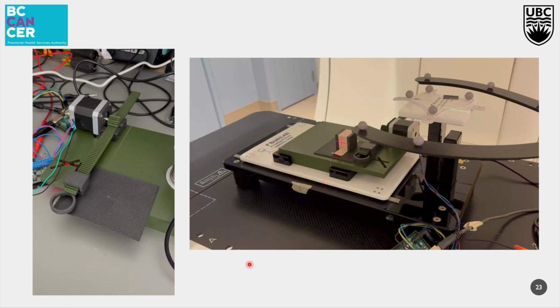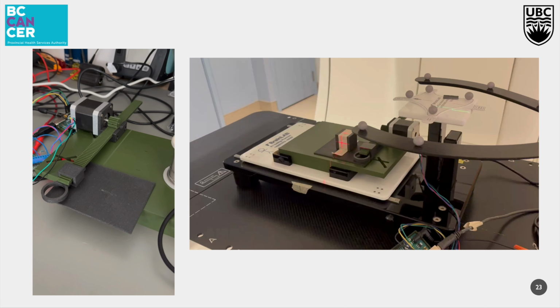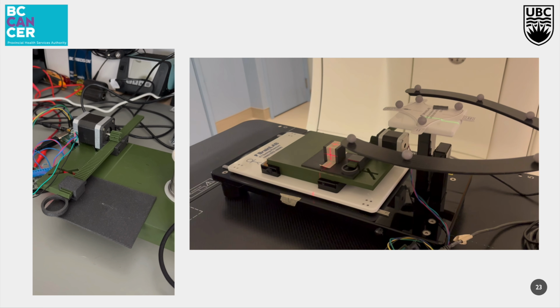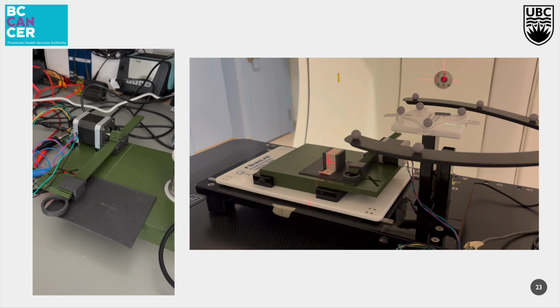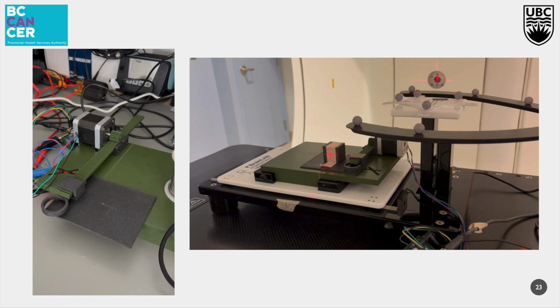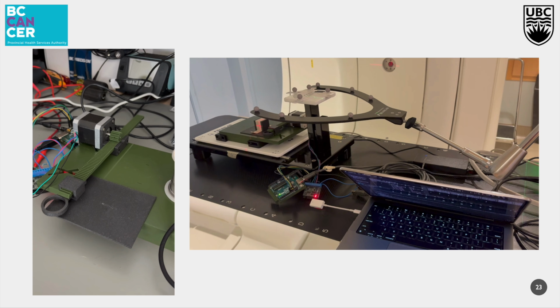So to see how exactly this actually worked, here on the left we can see a little video showing the cardiac phantom alone doing its little heart beating motion with an example trace. And here we can see the two phantoms moving in conjunction. Now here we do have it set up so that the cardiac phantom is moving perpendicular to the respiratory phantom, which is not how the experiments were done. But you can see the idea of the respiratory motion and the cardiac phantom motion being simulated simultaneously.